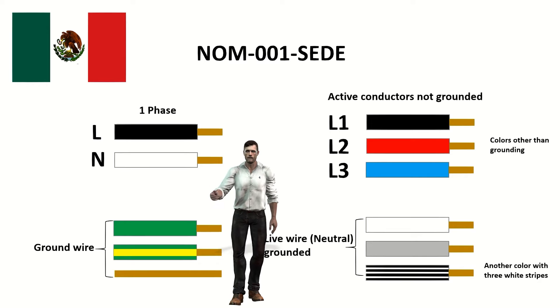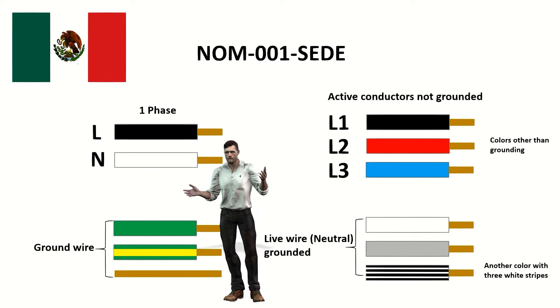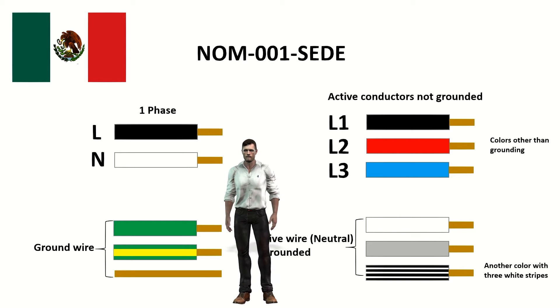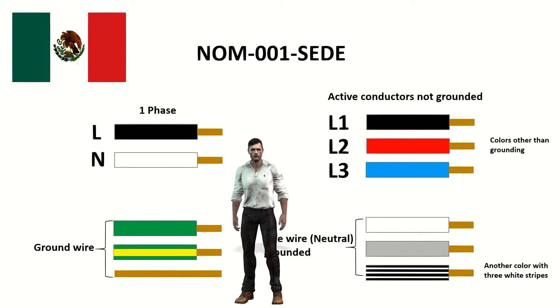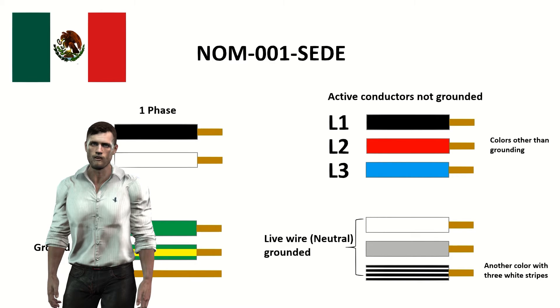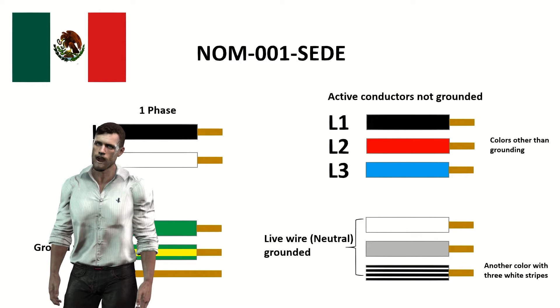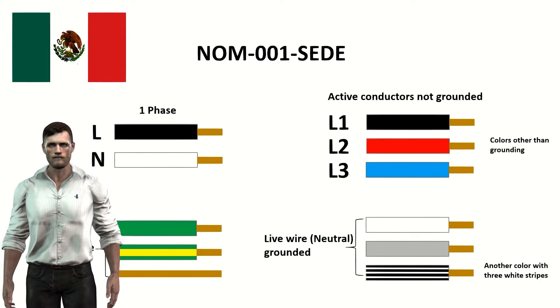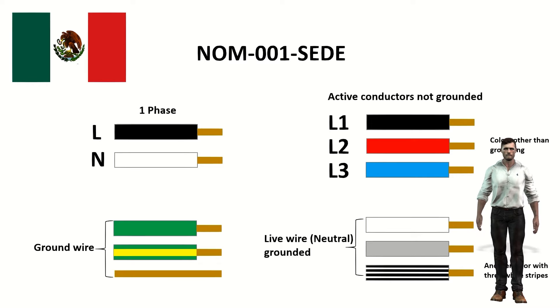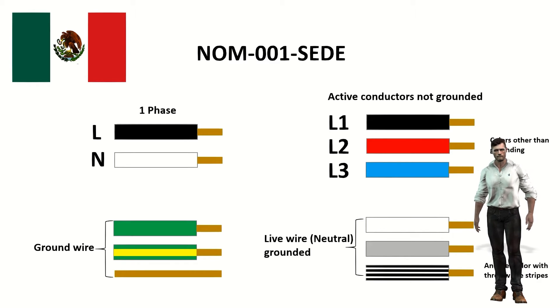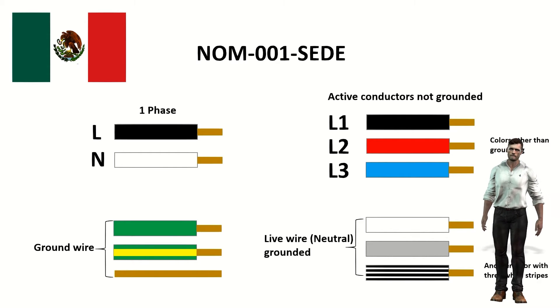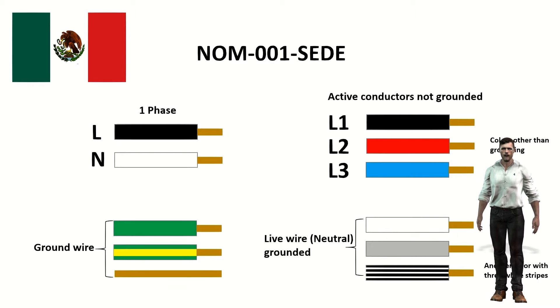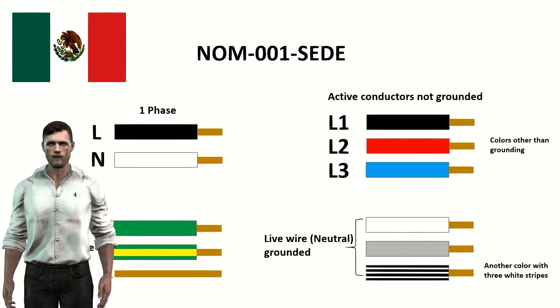The National Electrical Code also has influence in other countries of the American continent. In Mexico, the official Mexican standard NOM-001-SEDE establishes the color code of the equipment grounding conductors as well as the grounded power cable, which is normally the neutral. The grounded neutral can have the colors white, gray, or a color other than green but with three white stripes. The protection or ground wire is green, green and yellow, or bare copper wire. In a single-phase installation, black is used for the active cable and white for the neutral cable. For a three-phase installation, the live wires must take colors that differ from the grounded neutral or ground wires, for example black, red and blue.